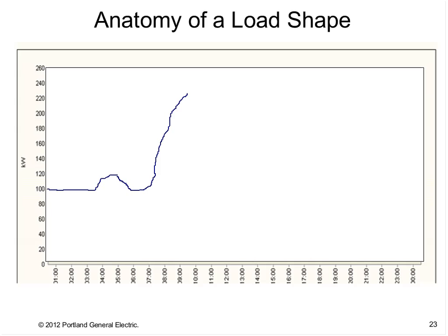For the rest of the day, while people are working, your load pretty much evens out till close to 5 o'clock. At that time, you have a chiller come online, and usage goes up a bit. Then right after around 5, people start leaving, things get shut down, and your usage starts to drop.